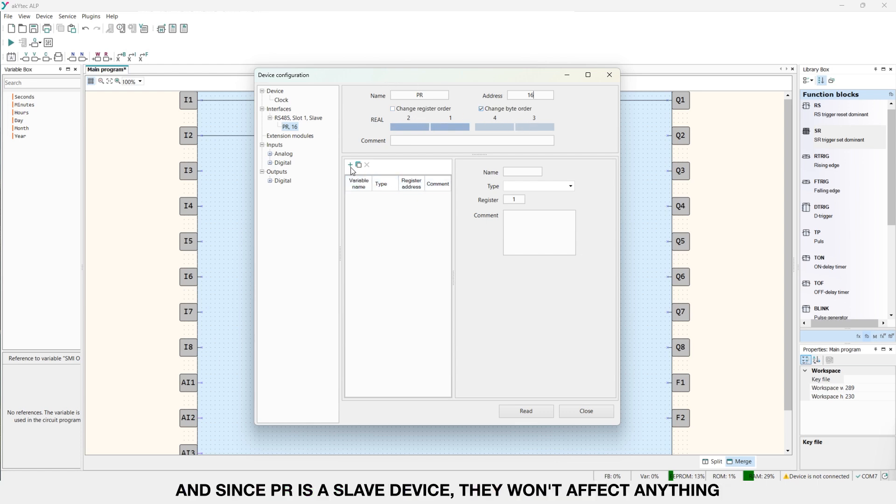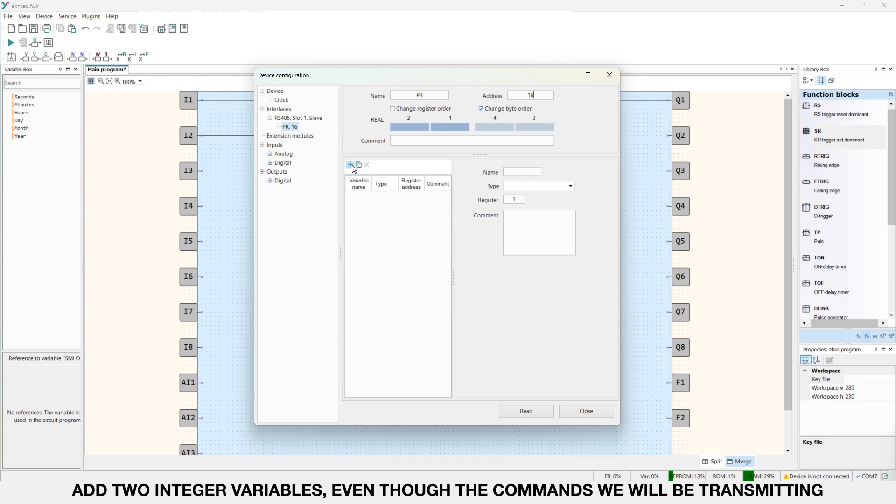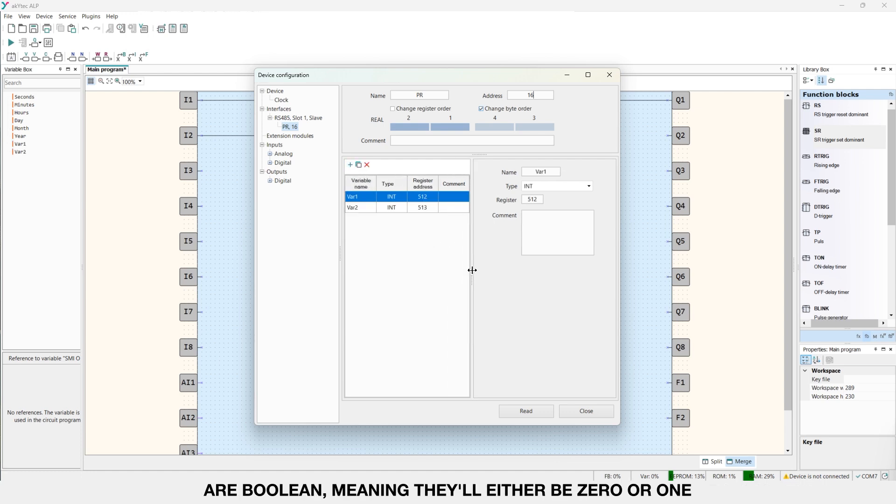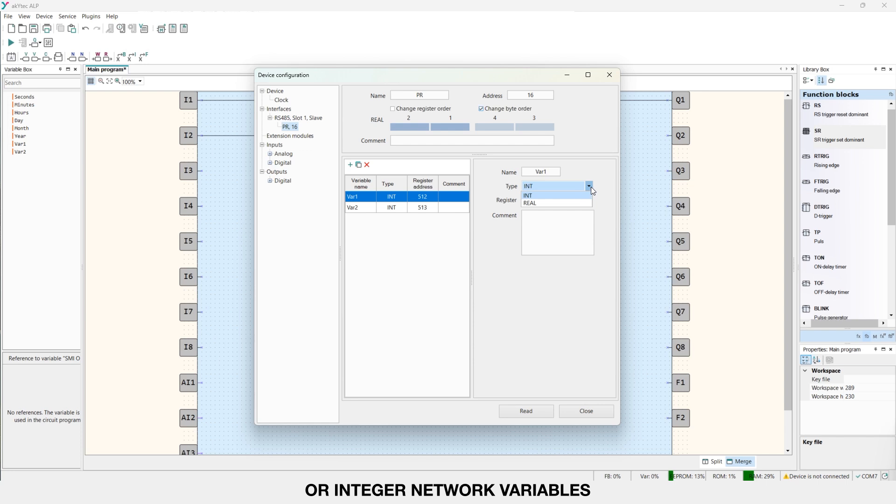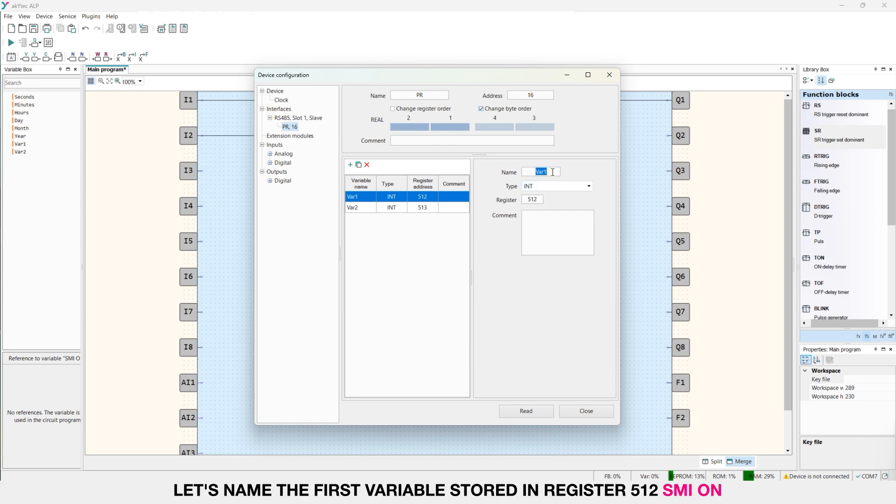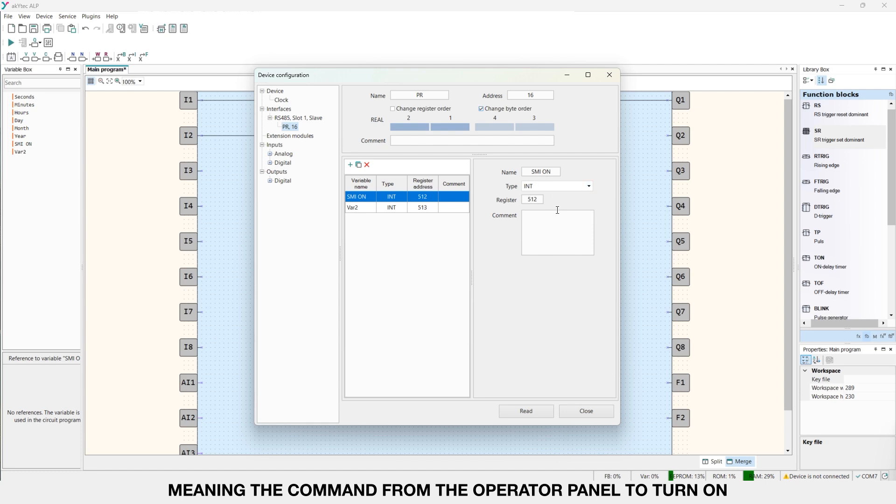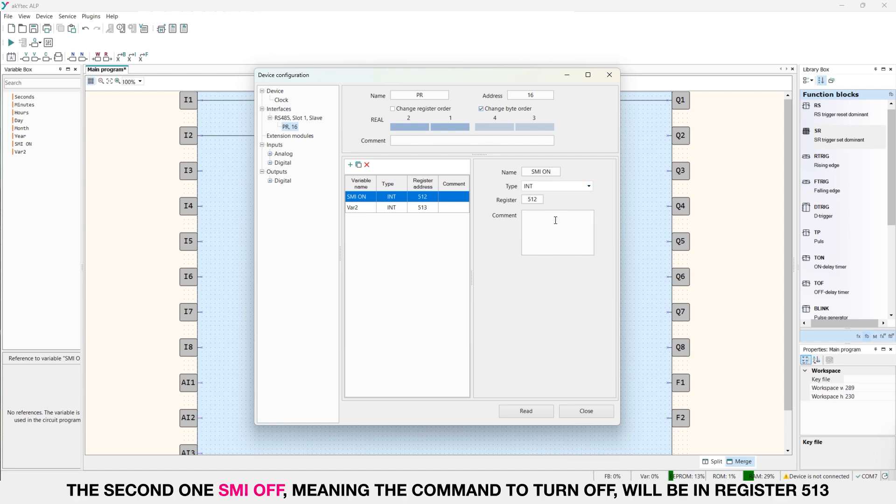Add two integer variables even though the commands we will be transmitting are boolean, meaning they will either be 0 or 1. This is because the PR as a slave device can only work with real or integer network variables. Let's name the first variable stored in register 512 SMI on, meaning the command from the operator panel to turn on. The second one SMI off, meaning the command to turn off, will be in register 513.